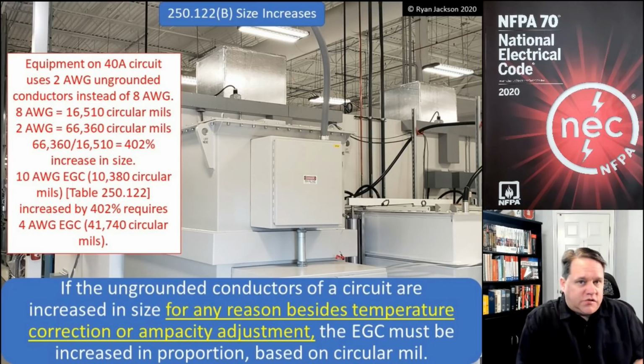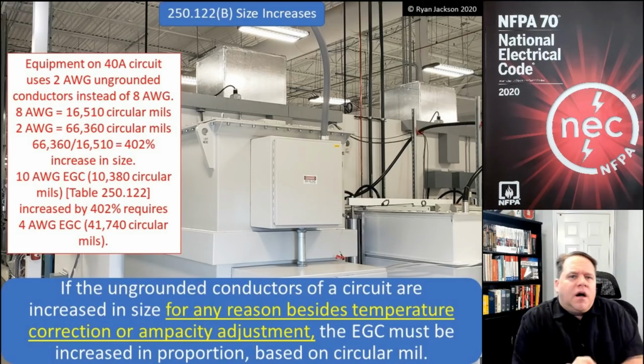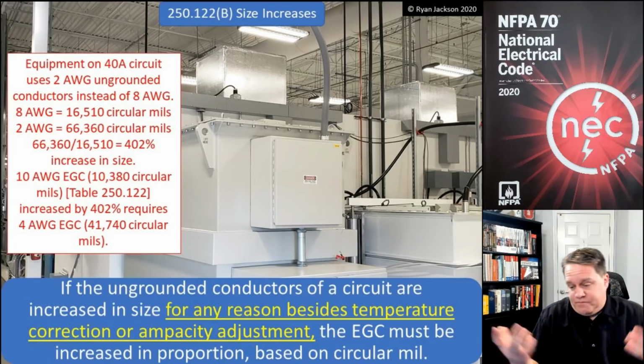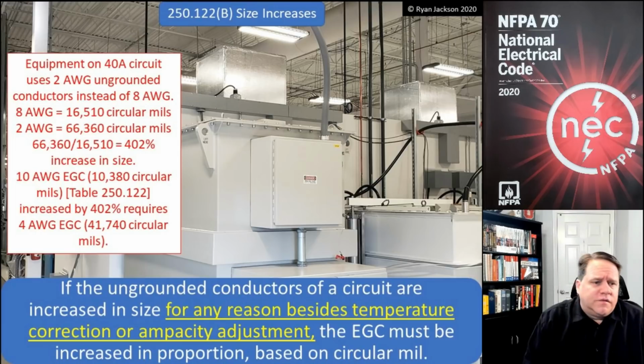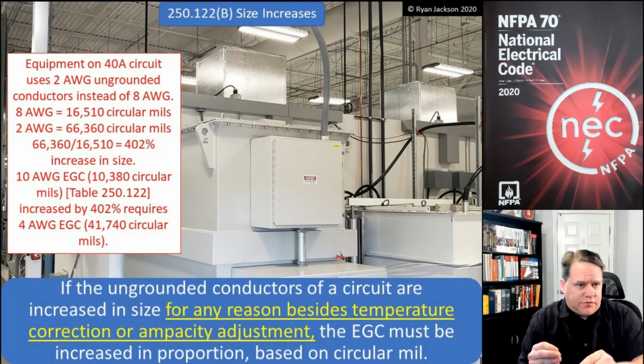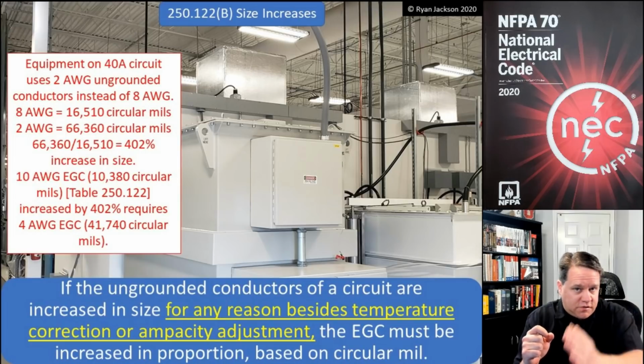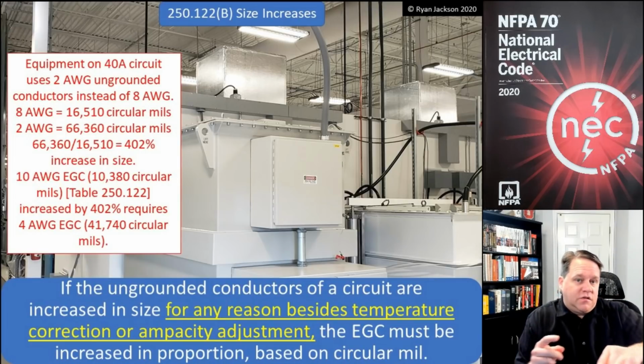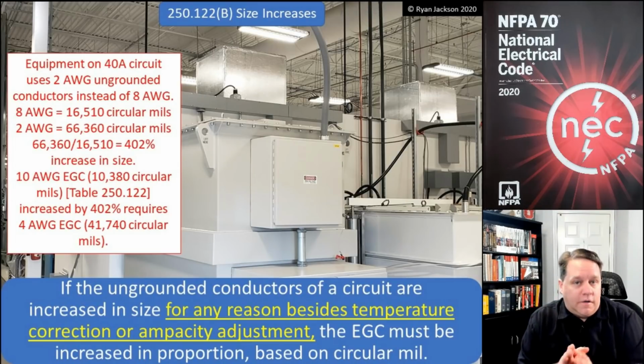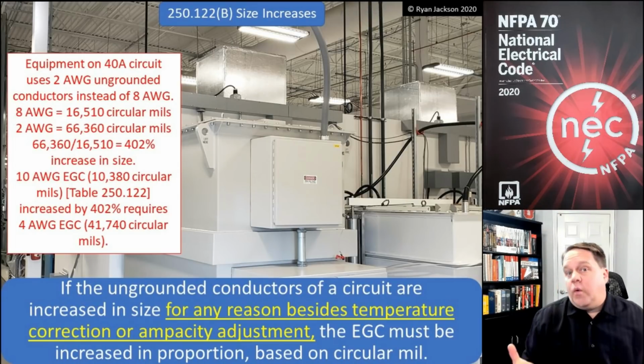This is not just for voltage drop. Maybe I installed larger wires because that's all I had on my truck. I would have loved to install 8 gauge wires to this machine, but all I had was some 2 gauge wire. So that's what I installed. Now, that's not a voltage drop concern, but one thing that it will do is it will ultimately increase the amount of current that is delivered during a fault, right? If I increase the ungrounded conductors from 8 to 2, then I decrease the resistance, which increases the current during a fault. Now, normally we would say that's a good thing, right?